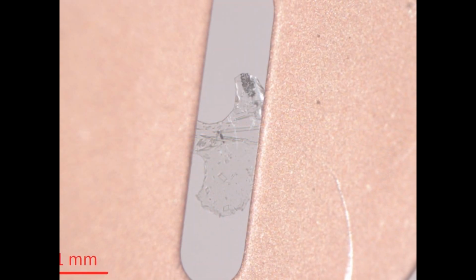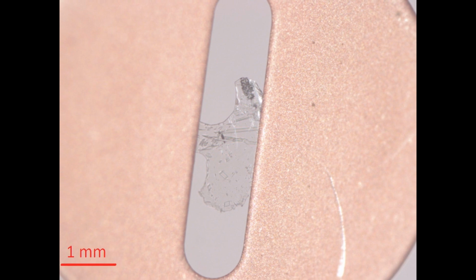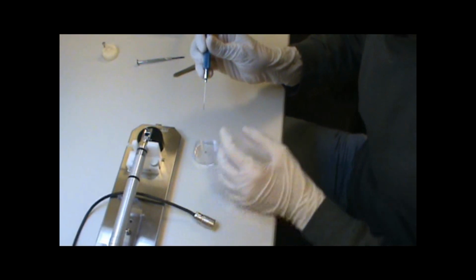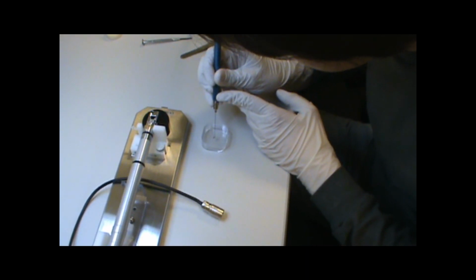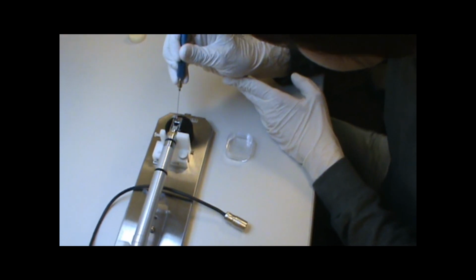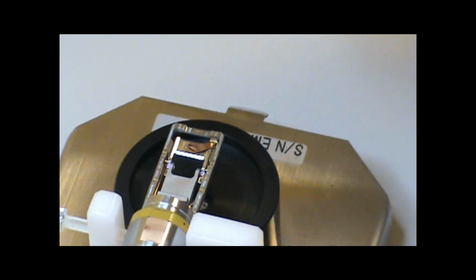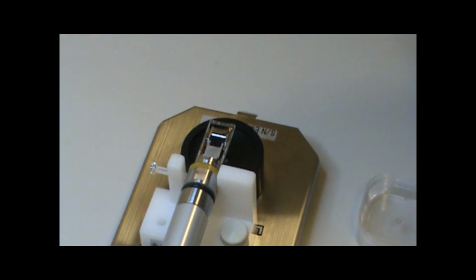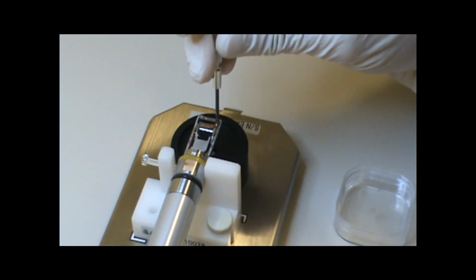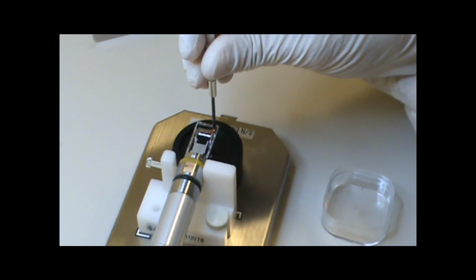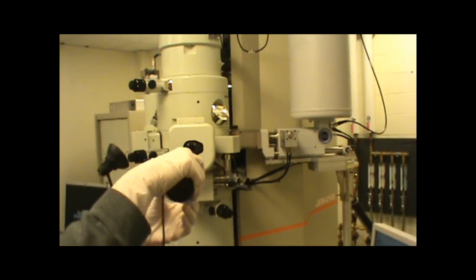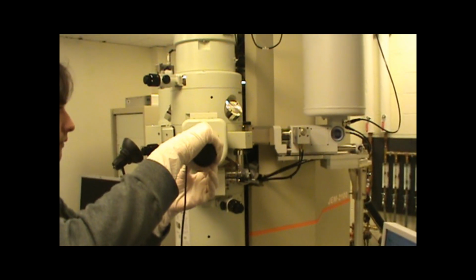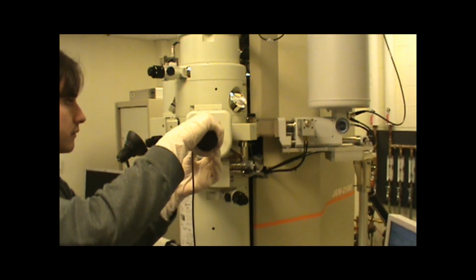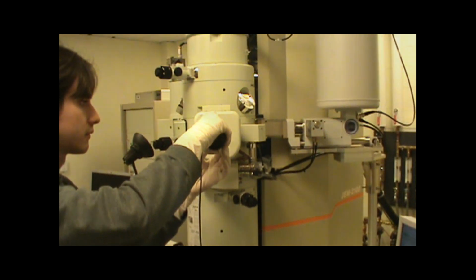A TEM specimen has to be electron transparent, meaning that it has to be thin enough to transmit sufficient electrons such that the intensity can be detected beyond the sample. Usually the thickness of a TEM specimen is lower than 100 nanometers. To insert the specimen into the microscope stage, it is placed on a specimen holder and then the assembly is inserted into the TEM. Once inside, the specimen holder can be moved laterally to look at different areas, vertically to focus the image, and tilted to look along a particular direction.